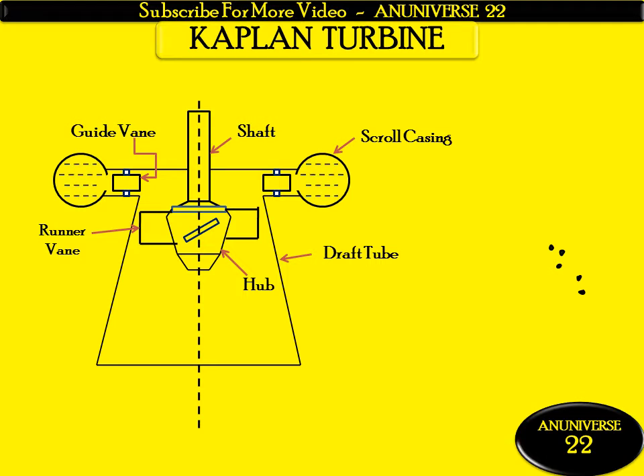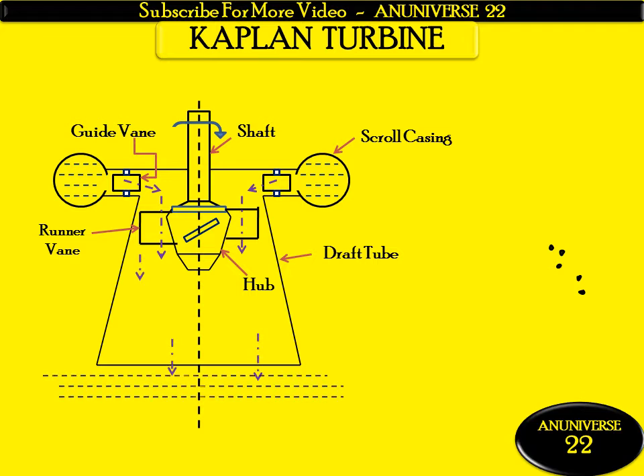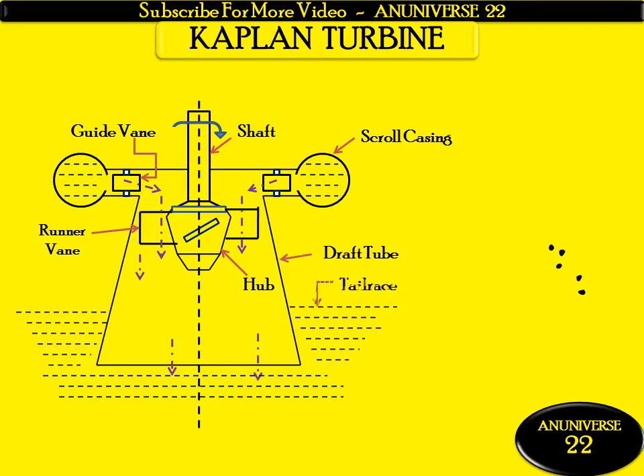Water starts from the scroll casing and passes through the guide vanes. The water that is discharged is parallel to the axis of the shaft. As the water strikes on these vanes, the runner starts to rotate and it will rotate the shaft coupled with it. Finally, the water is discharged through the draft tube towards the tailrace. This is the tailrace — the top surface of the water is the tailrace.